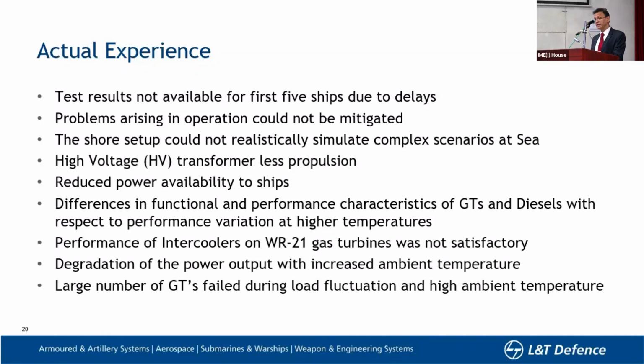On a particular plant, there were 2 different gas turbines and 2 diesels, expected to have a certain characteristic at higher temperature. But none of these prime movers had a consistent characteristic - all the gas turbines had different load power generation ability at higher temperature, and the same happened with the diesel engines. This created problems for the power management system, which could not sustain them.